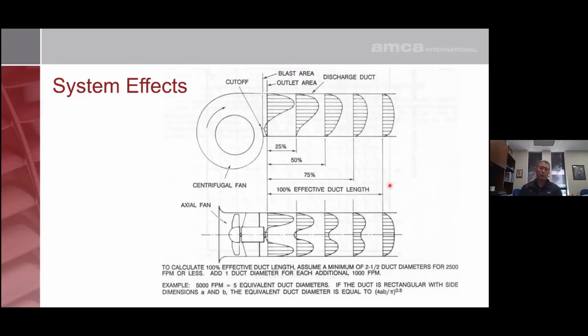So on the discharge side of the fan, again, we talk about air. Air has mass. Mass wants to go along a straight line and wants to hug the outside of the volute shape of the fan housing. So when it leaves the fan, most of the air is at the top portion of the housing. Very little of the air is at the bottom portion of the housing. And unless you have 100% of effective duct length to allow for that velocity profile to even out, you will not get full static pressure regain, and that fan will not perform as cataloged. We'll see that in our video a little bit later. What is effective duct length?